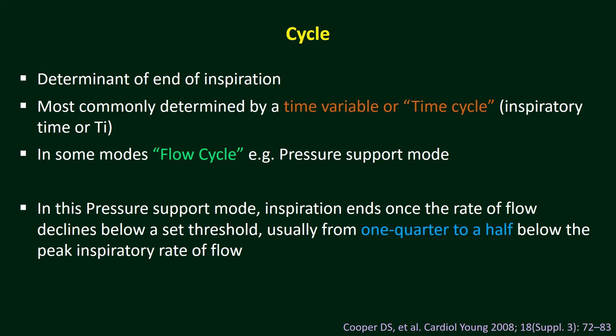This is the pressure waveform in pressure support ventilation, inspiration, expiration, inspiration, expiration, and this is the flow curve in pressure support ventilation. This is inspiration and this is expiration, and this is the volume curve. So what happened here? At the beginning of inspiration, flow reaches its maximum to reach a peak pressure of this pressure support level, what we have set in the ventilator. So if we set a pressure support of 15 or 20, up to this point will be reached. So maximum flow will be achieved to reach peak pressure up to this level, and then flow will start to decrease gradually, as this is pressure limit.